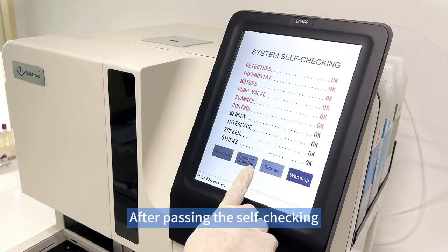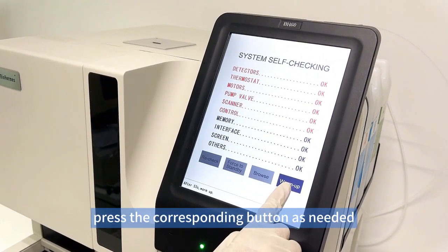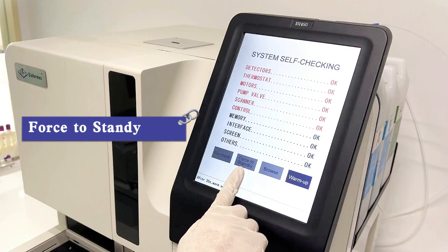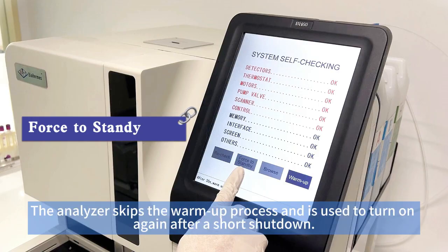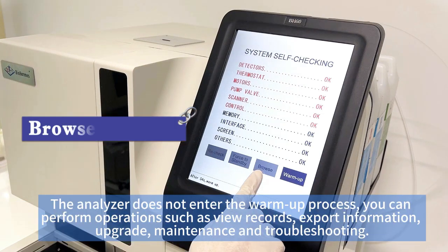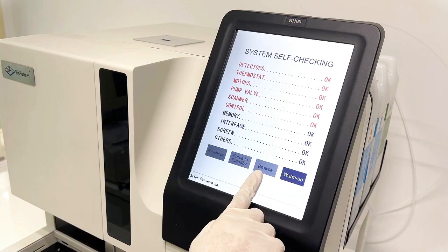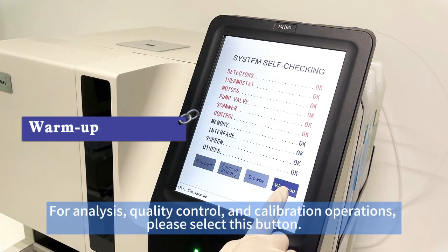After passing the self-checking, press the corresponding button as needed. Forced to standby: the analyzer skips the warm-up process and is used to turn on again after a short shutdown. Browse: the analyzer does not enter the warm-up process. You can perform operations such as view records, export information, upgrade, maintenance and troubleshooting. Warm-up: for analysis, quality control, and calibration operations, please select this button.